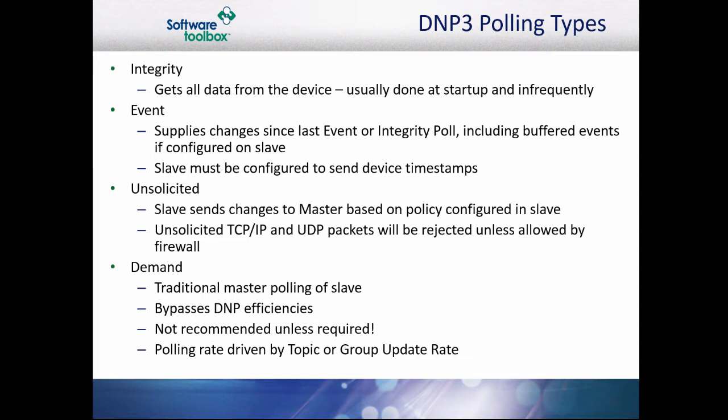Unsolicited messages are sent by the slave on an event or data change if it is configured to do so, without a poll request from the master. The timing and deadband for these messages are handled by the slave. Please note the importance of firewall settings — if you are using unsolicited messages and your firewall does not have the proper exceptions, your unsolicited packets will be rejected.